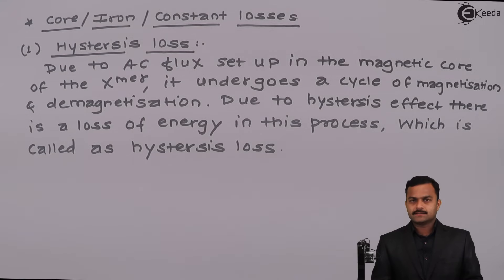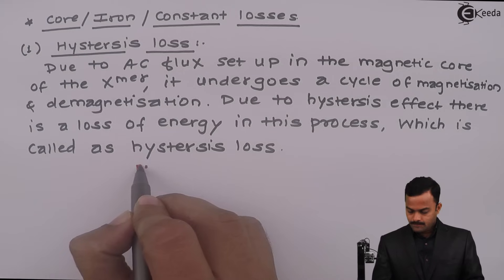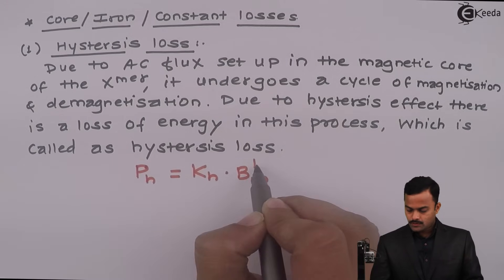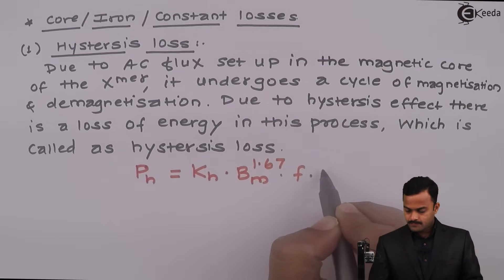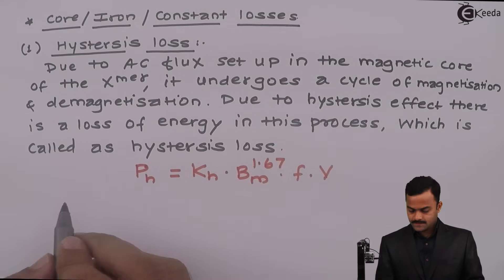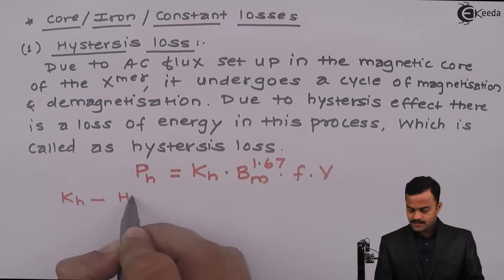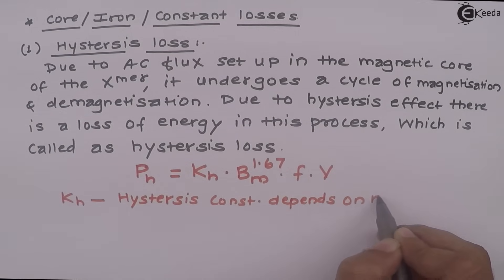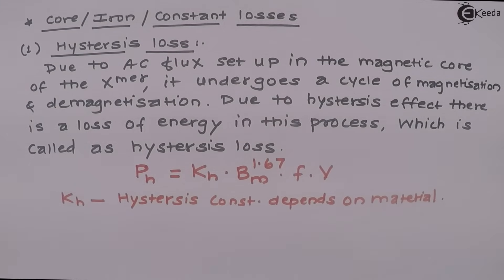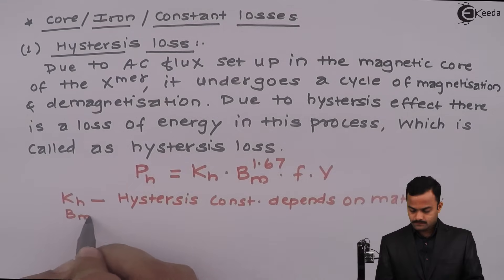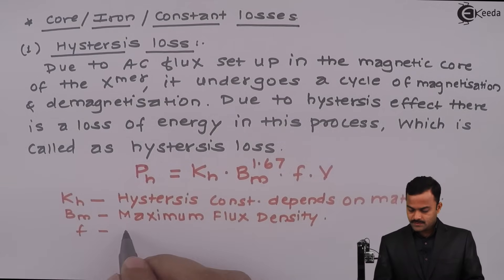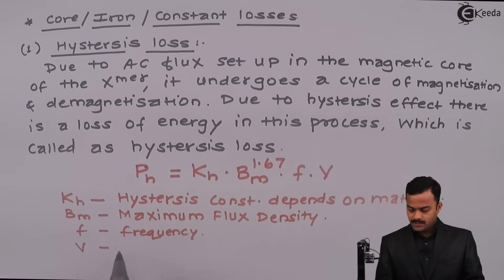Hysteresis loss depends upon what type of magnetic material we are using. The formula is: P_H = K_H × B_M^1.67 × F × V, where P_H is hysteresis loss, K_H is the hysteresis constant which depends on the material, B_M is maximum flux density, F is frequency, and V is the volume of the core.